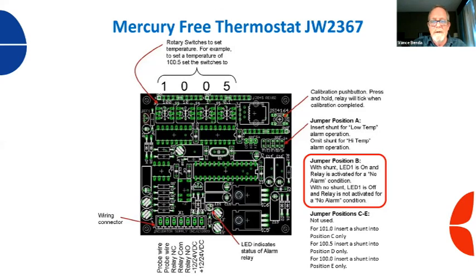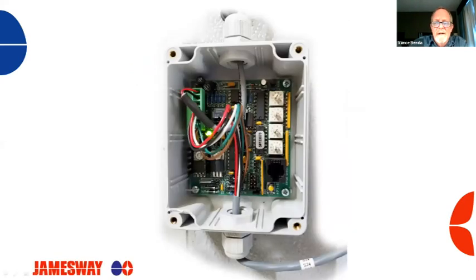Much better. So here's our high temp alarm box, an actual picture of one. As I said, there are rotary switches up here, and if you look, you can see this one's set on 1 0 1 0. That's 101 degrees. I'm assuming this is on the roof of an incubator. Here's your calibration test button, your calibration button. And it's hard to see, but there's your shunt right there in the B position. And there's your LED lit up. That tells me that this is not only mounted on the roof of an incubator, the incubator is running at 101 degrees and there's no alarm, so everything's good.